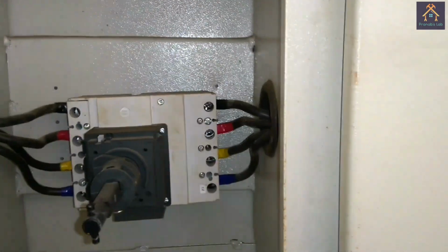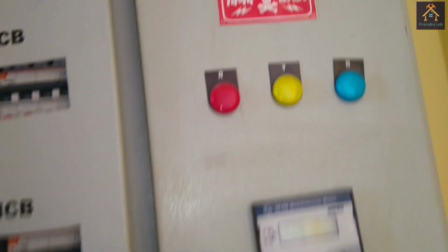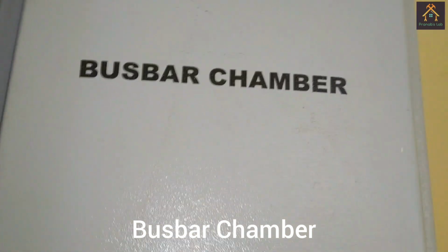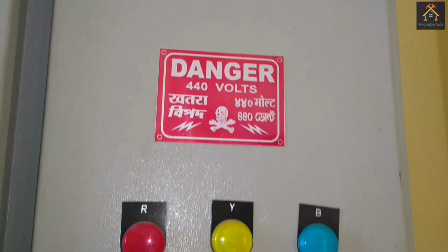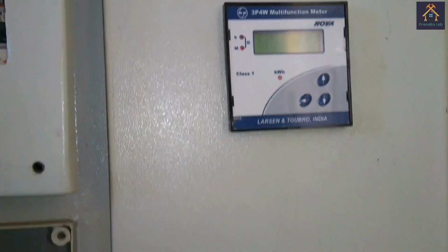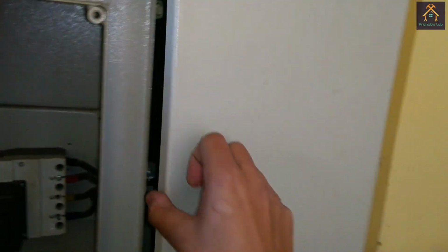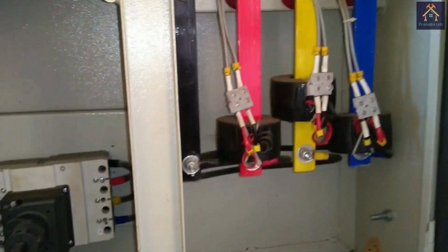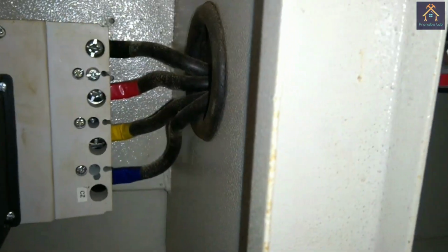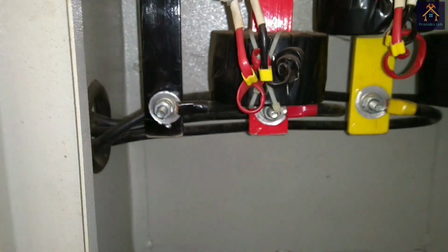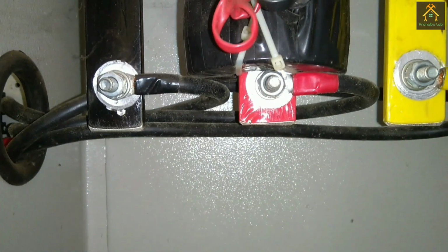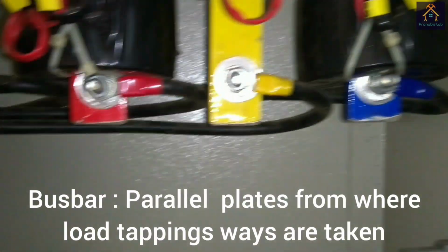The 4 outgoing cables from the MCCB are inserted into the next chamber, that is the busbar chamber. It is the most vital part of the panel. After opening the door, you can see the 4 outgoing cables from the MCCB are inserted into the busbar chamber and connected with the 4 different buses by using the GI lug and nut bolt.